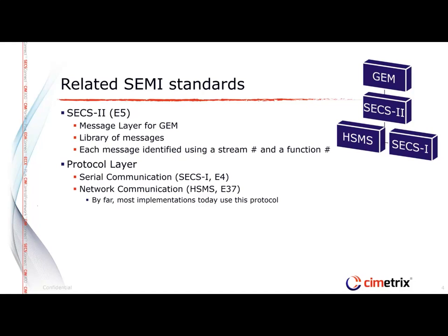There is also a protocol layer with two possible options. One is serial-based communication using RS-232, called the SECS1 standard. The other is network-based communication using Ethernet technology, called HSMS, and that is what everybody is really using today because network communication is fast and easy to set up.